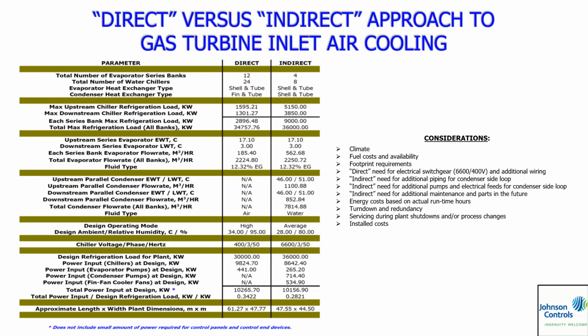We were leaving the evaporators at 3 degrees Celsius, which is, run that number, what is that in Fahrenheit? 36. Yeah, okay, 36 degrees. Remember, this is water temperature. On this project, all we were doing was the chillers and the fin-fan coolers and the pumping skids. We weren't providing the air houses. The air houses is where you bring the cold water to it, and then you got the air going through it, and then it leaves the coils at 40 degrees plus or minus, get it cold. We weren't doing the air houses on this job. Okay, we were just doing the chillers.